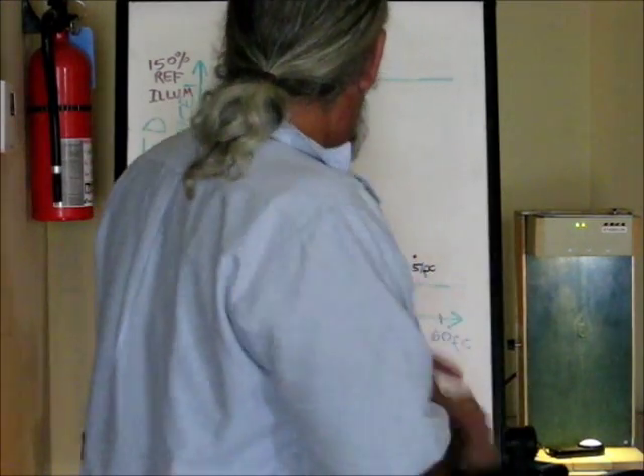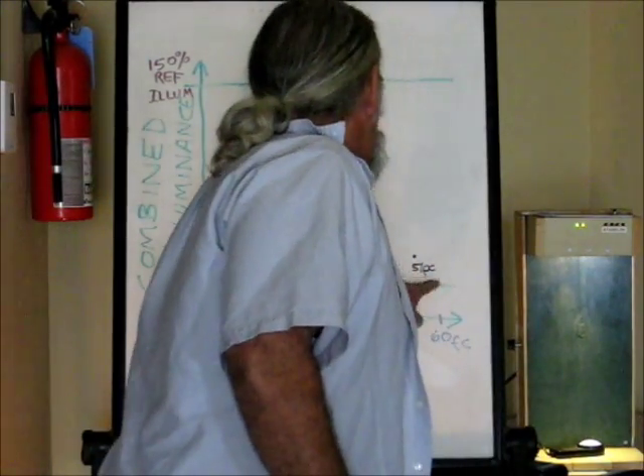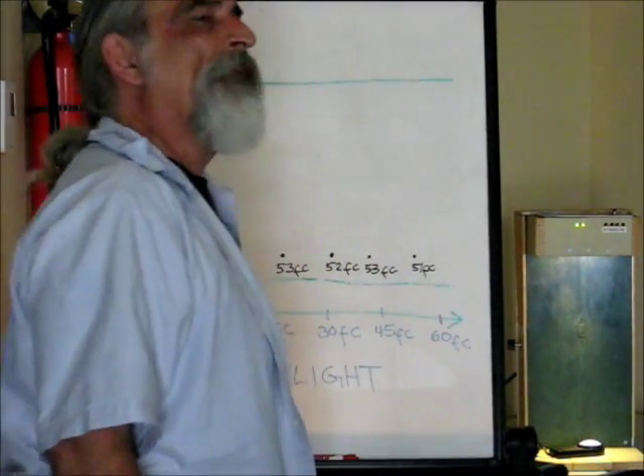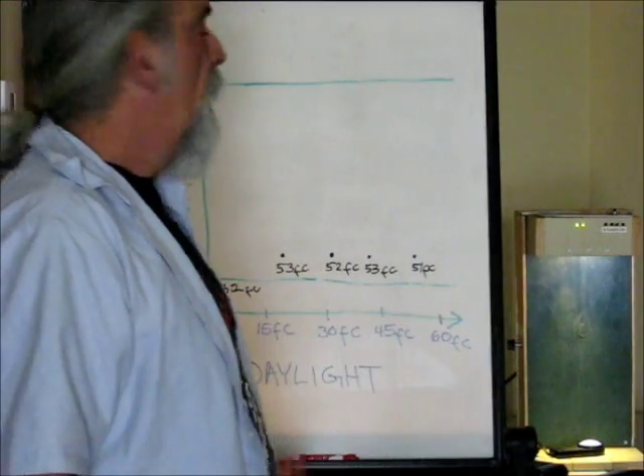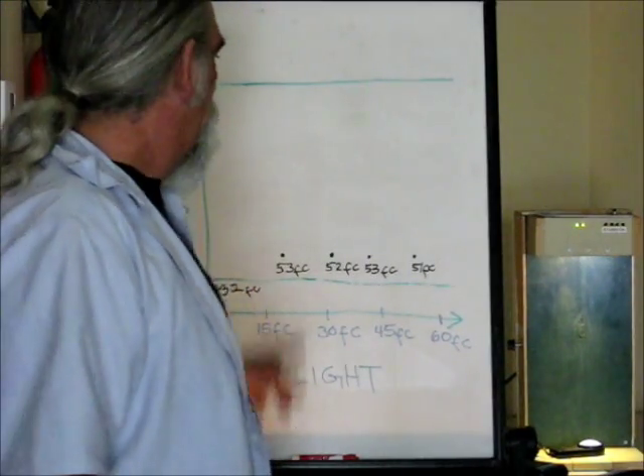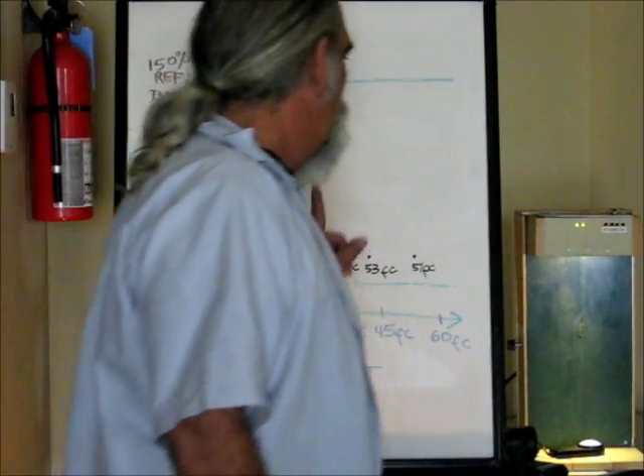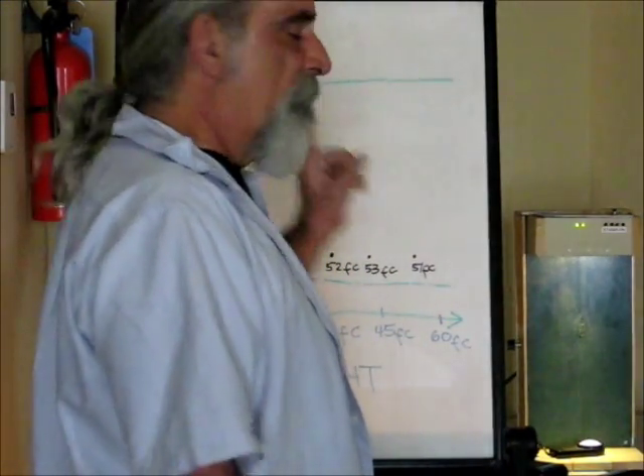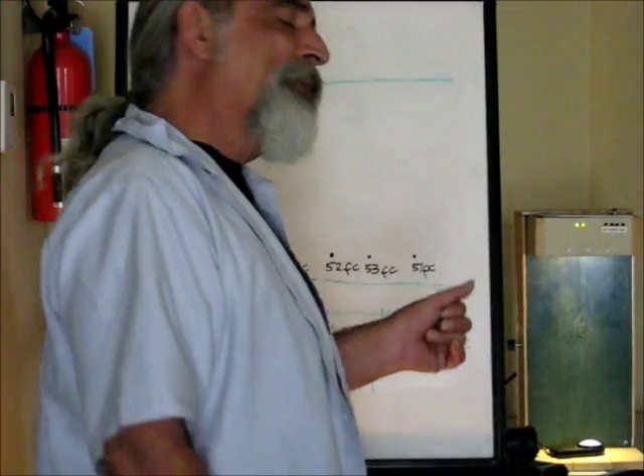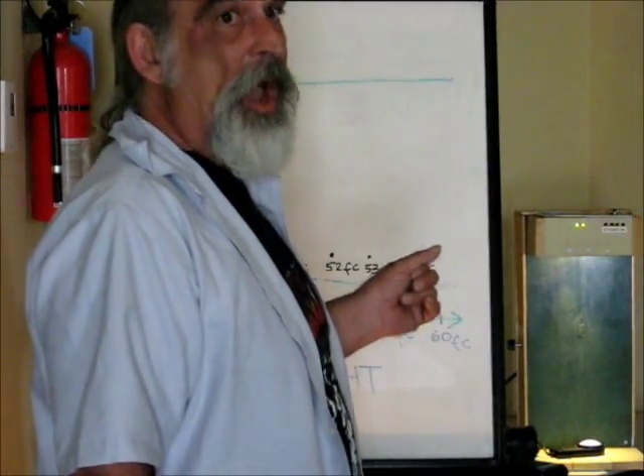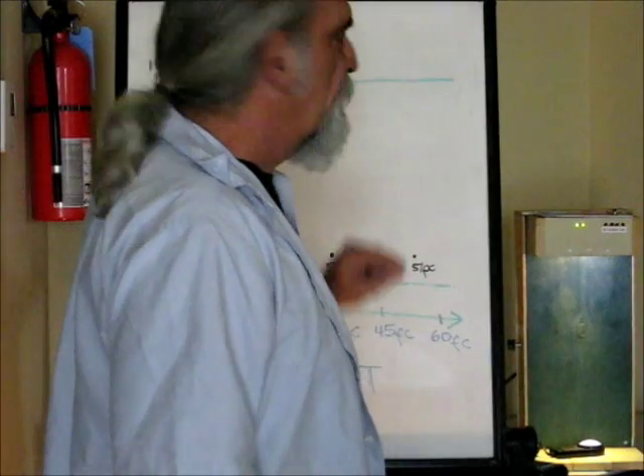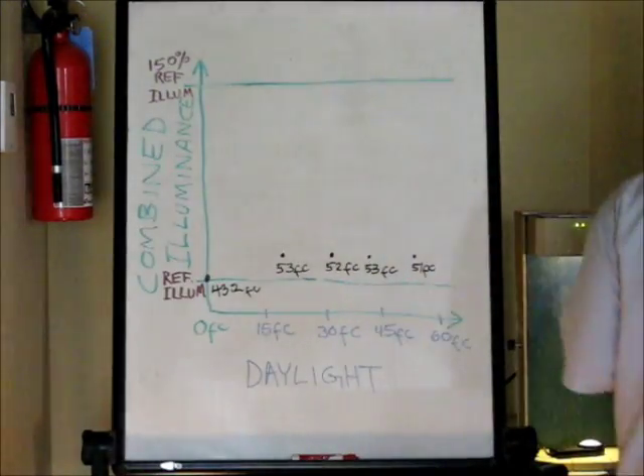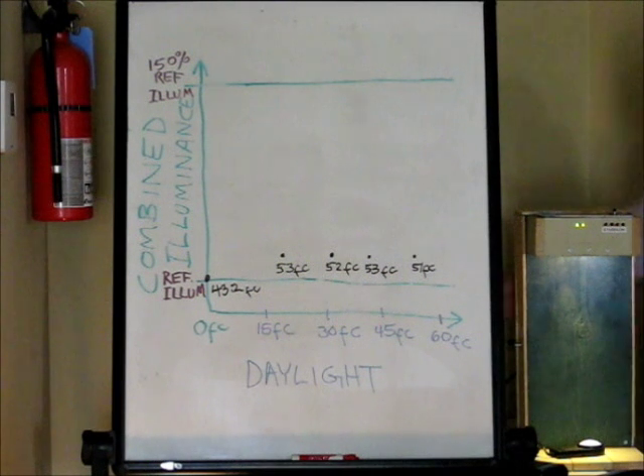Is 51 foot candles better than our reference illumination? So it's perfectly good for a full daylight test now, isn't it? Yeah. It's not even excessively high. I'm going to do an extra step that is not required by the test for the test form. I'm going to rotate the knob backwards. I'm going to let the sun go back down and let the stages of lights turn on. And I can tell you they're going to turn on at just about the same daylight levels as before.